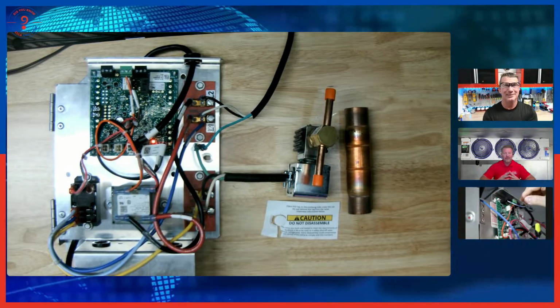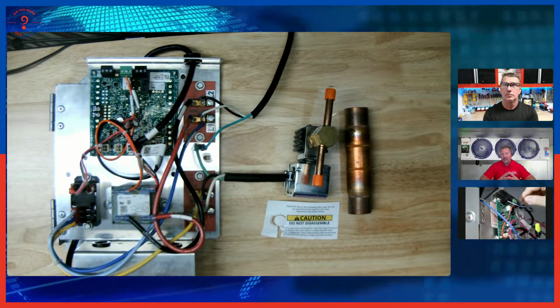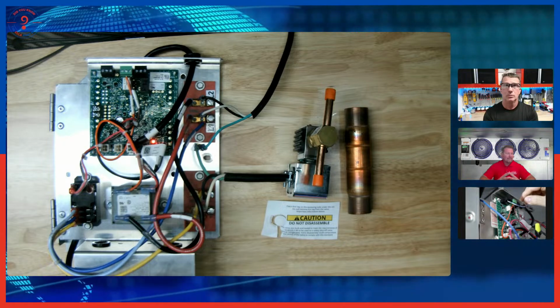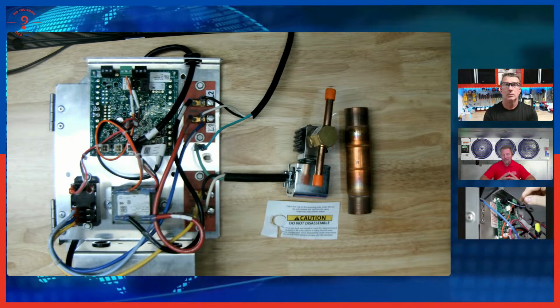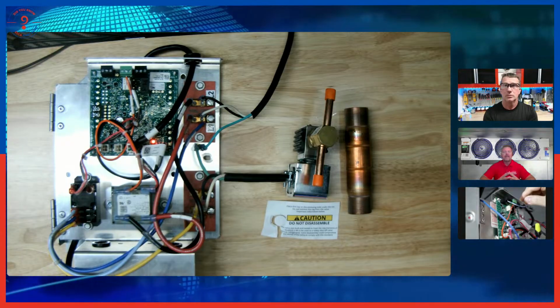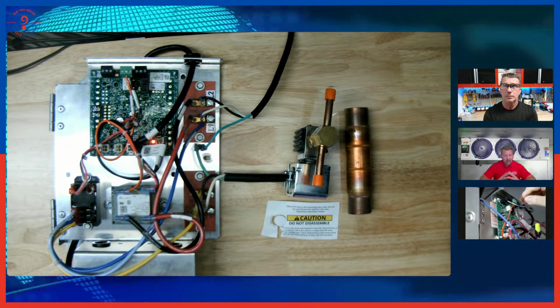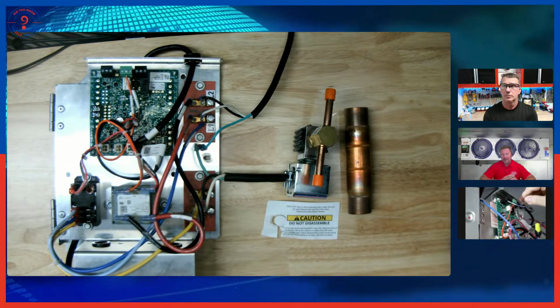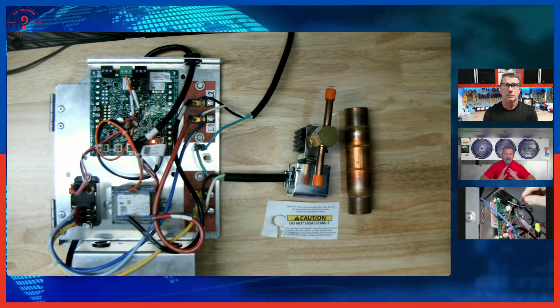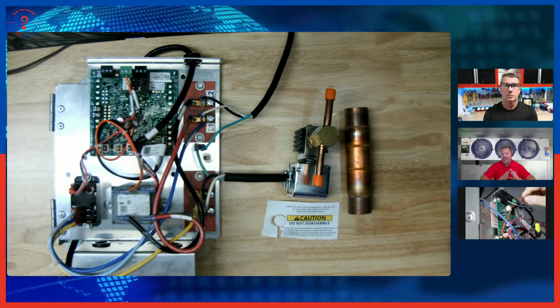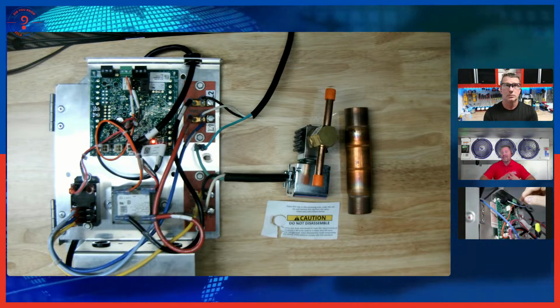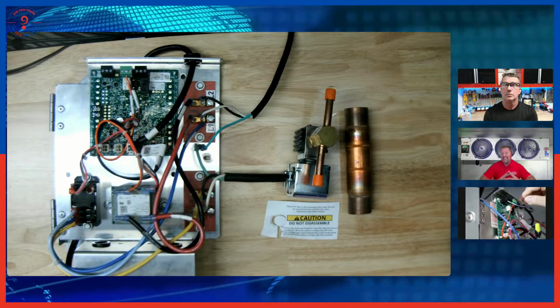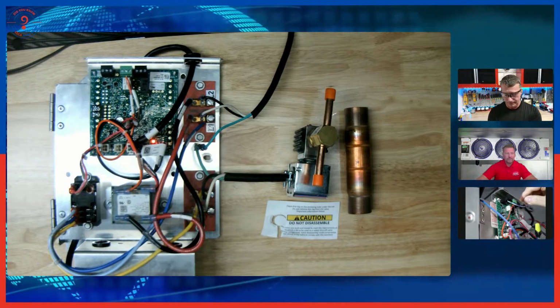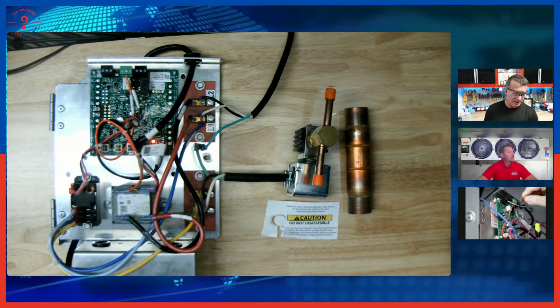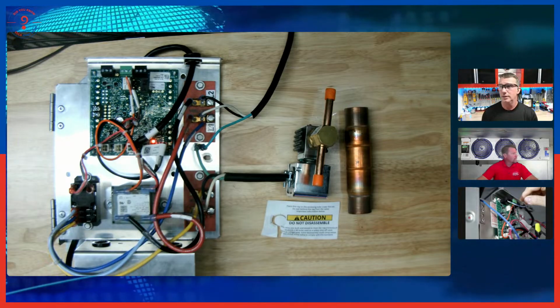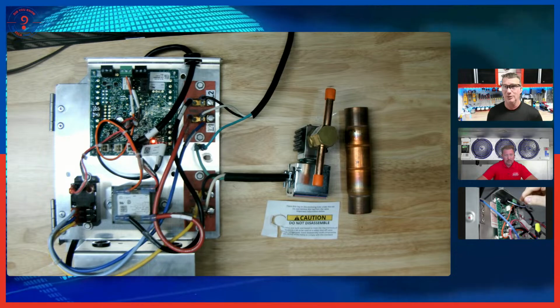So it is critical to stress that, yeah, you might carry a Sporlan solenoid on your truck with an MKC1 coil, but it shouldn't be used. You need to use the proper equipment in this case. UL mandates it. It's the only way that we can guarantee that your system, if it develops a leak, will be safe. Gotcha. I had been testing this before the show, and I actually set it off quite a few times.